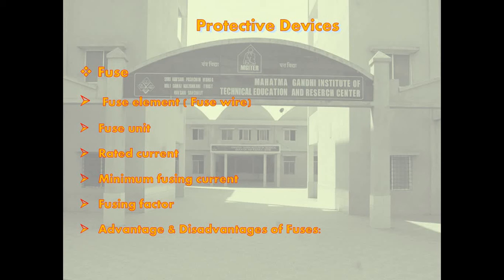But it has disadvantages. Time is lost in rewiring or replacing a fuse after operation. It is not possible to employ secondary backup protection to fuses. The inverse time current characteristic of a fuse cannot always be correlated with that of the protected apparatus. On heavy short circuit, discrimination between fuses in series cannot be obtained unless there is sufficient difference in the size of the fuses concerned.